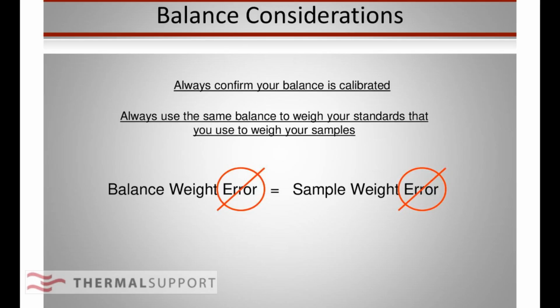And then, when you're at that point, remember, we've talked about this before, you've got balance considerations. If you're going to weigh out a sample, you want to make sure it's right. You want to make sure your reference material is right. You want to use a new reference material if possible. And you're going to make sure that you use the same balance with your samples as reference materials.